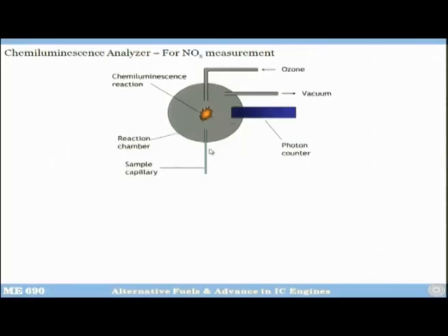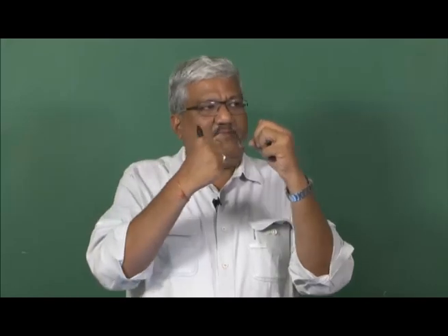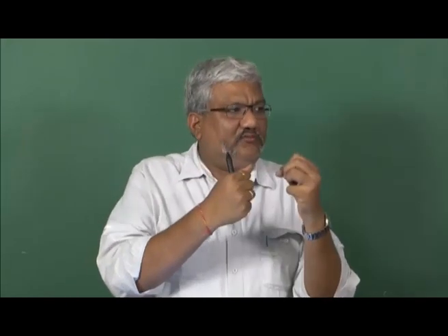So, now what happens is that you put the sample, and here you have the ozone. Now, the sample may contain lot of other species also. There may be carbon monoxide, there may be water vapors and other things. So, what happens is that it is quite possible that the excited NO2 molecule is attacked by a water molecule. There may be molecular collision, right.